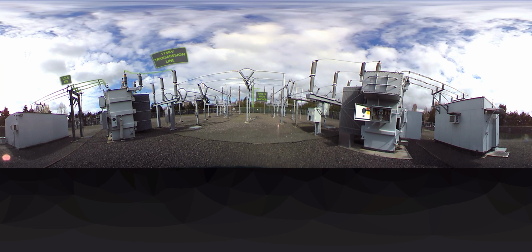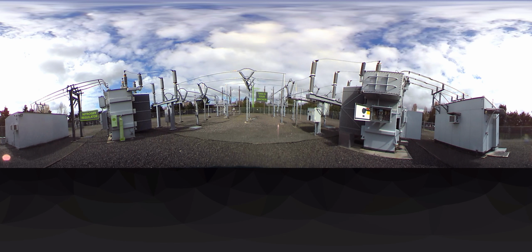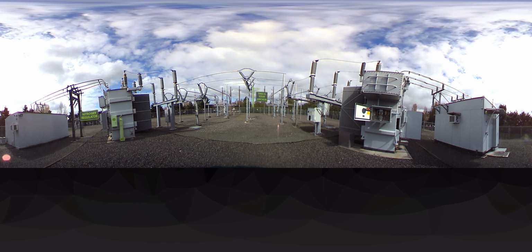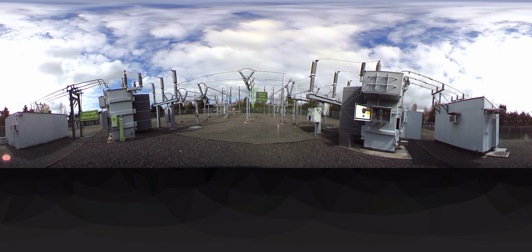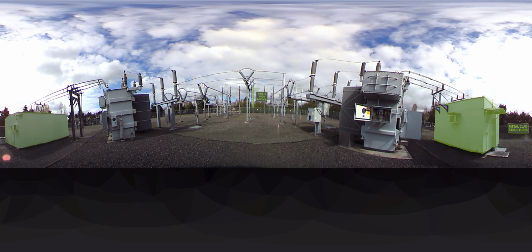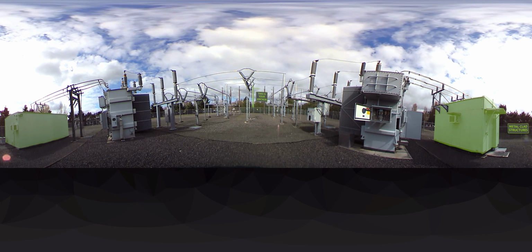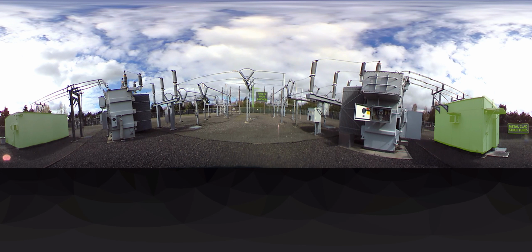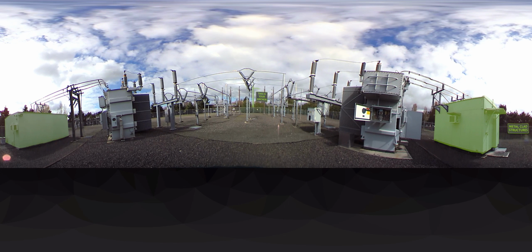Housed inside this box is a nitrogen regulator. The regulator keeps a nitrogen blanket on top of the entire transformer, thus preventing oxidation. This inert gas ensures no moisture can seep into the transformer, which could cause damage to the equipment. Now, if you continue to spin your camera to the left, you will see the two metal-clad structures at the low side that the newly transformed power leads into. Housed in these structures are the relays and controls for all the equipment we previously mentioned. And finally, the power exits the metal-clad structures via underground cables, which connect to distribution feeders.